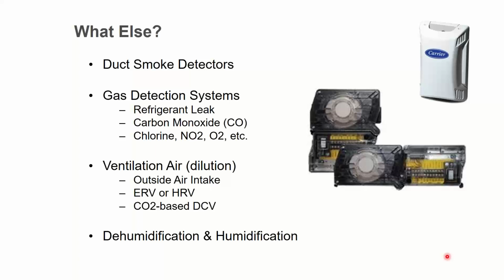Smoke detectors, commercially — some buildings require them all throughout the ceiling. But in addition, HVAC systems also require smoke detectors. If you have 2,000 CFM and larger, you're required by code to have a duct smoke detector. It's required by both the International Mechanical Code, which most states or municipalities adopt — in the case of Massachusetts, where many of you are following IMC 2015, it requires duct smoke detectors for all systems 2,000 CFM and larger. NFPA, the National Fire Protection Association, also requires it at 2,000 CFM.